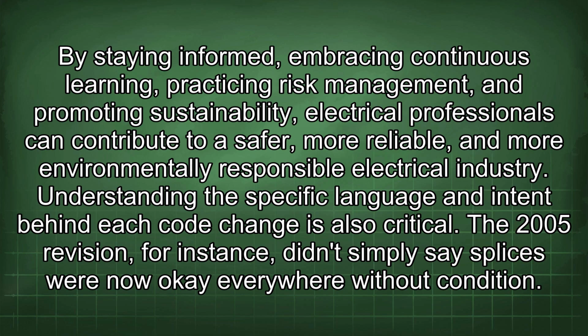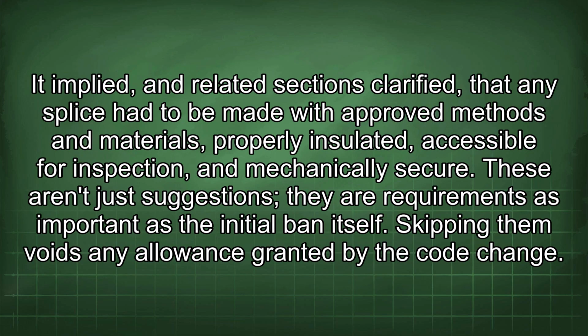Understanding the specific language and intent behind each code change is also critical. The 2005 revision, for instance, didn't simply say splices were now okay everywhere without condition. It implied, and related sections clarified, that any splice had to be made with approved methods and materials, properly insulated, accessible for inspection, and mechanically secure. These aren't just suggestions, they are requirements as important as the initial ban itself. Skipping them voids any allowance granted by the code change.